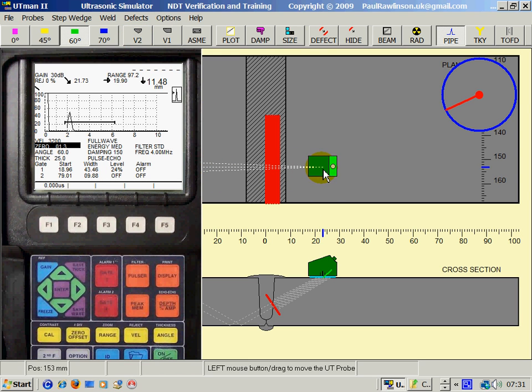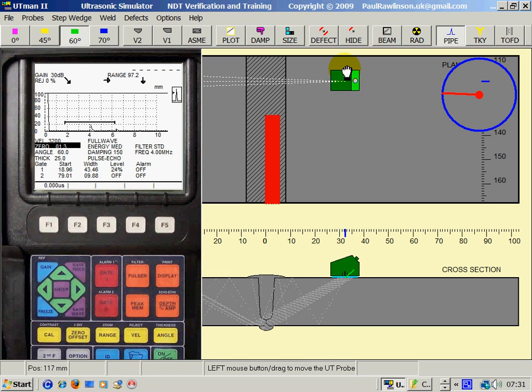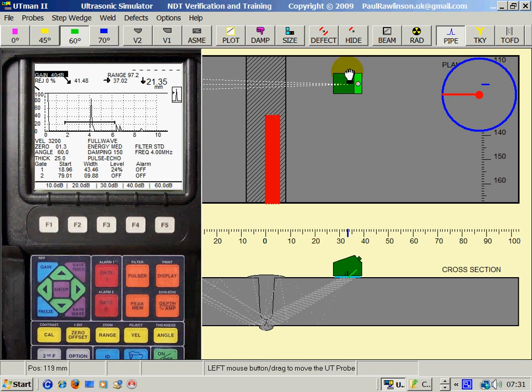Now you'll notice the readings we're getting. Let's just check it on the root. Increase the amplitude. Now this is telling us the depth vertical down is 20.86 millimeters. The standoff distance from where it's detecting this echo, which is the root, to the emission point in this distance here is 36.16, and the actual beam path, the distance the sound has travelled, is 40.49. That's the distance down here.